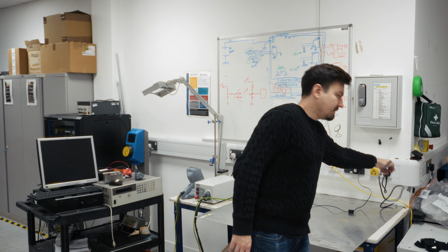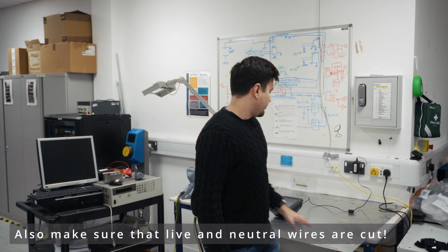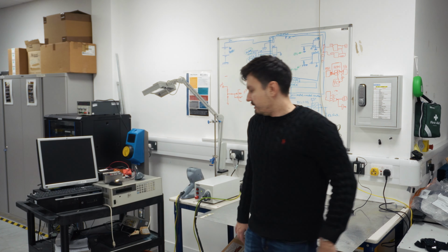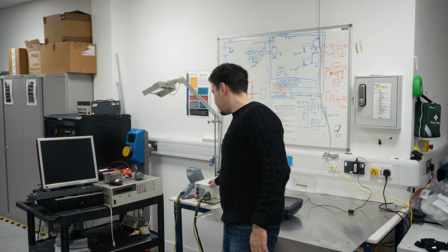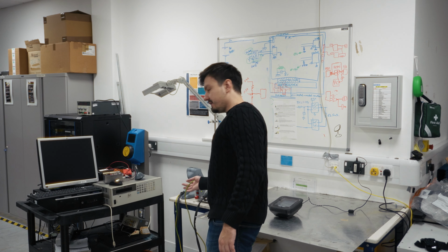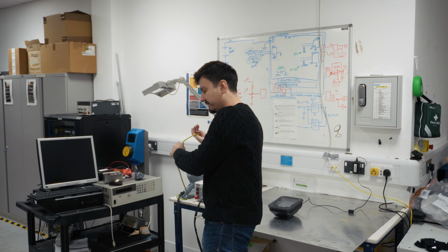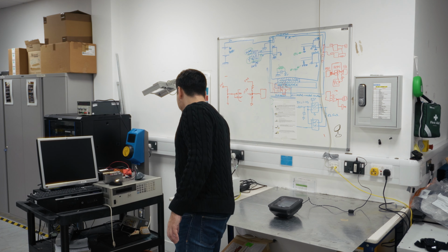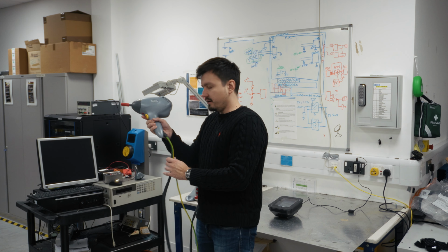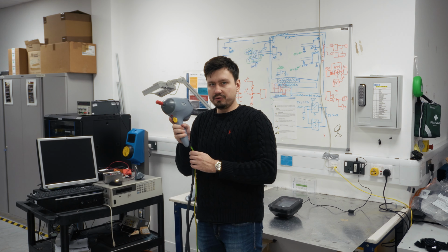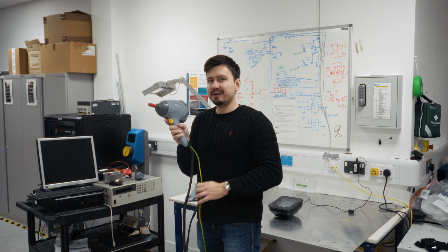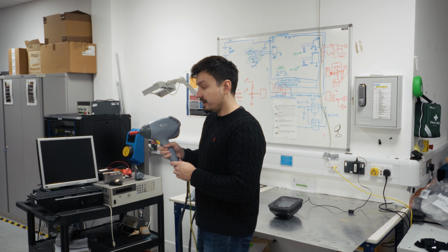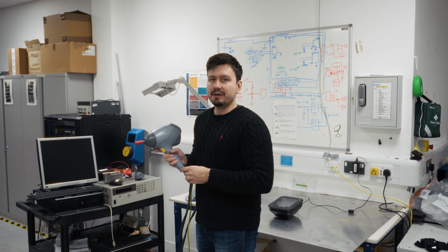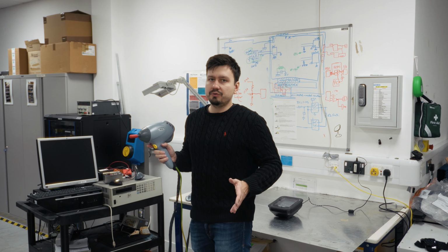You want to make sure it's switched, right? And similarly, we also need to make sure that our ESD apparatus that generates the spike is also grounded, and that is done with this earth lead that comes from the ESD gun itself. So it's very important to double check that both of those connections are present, otherwise you will be risking making wrong tests, so doing the test wrongly, getting wrong results, or even injuring yourself.